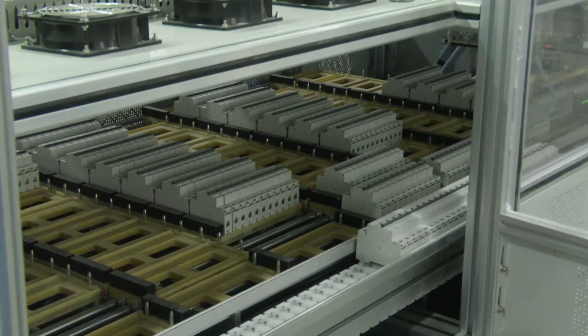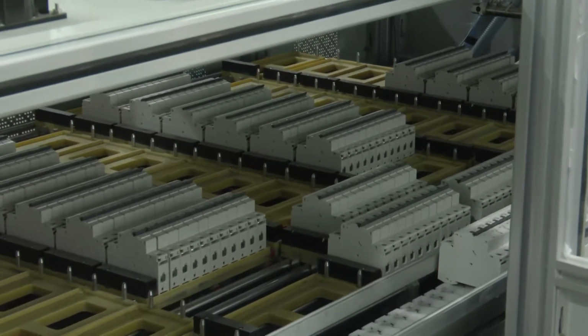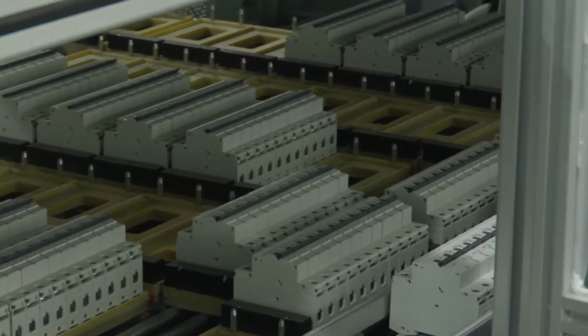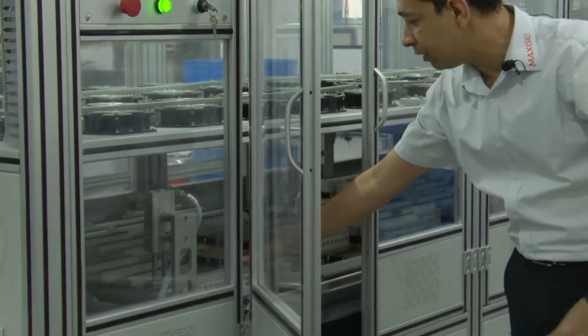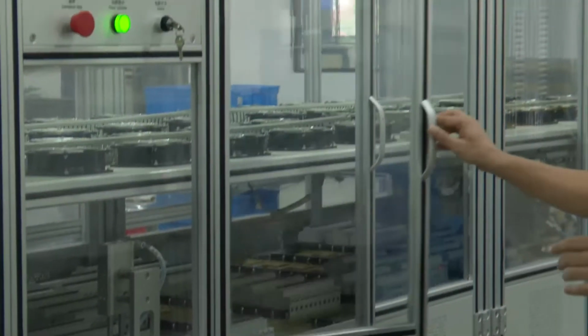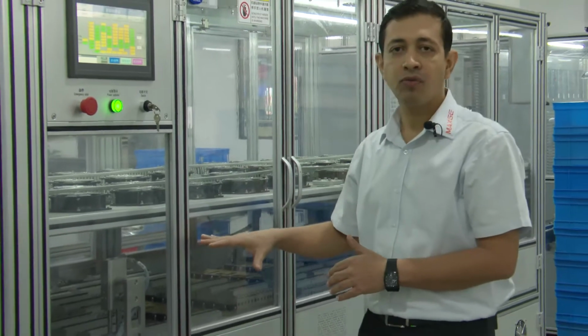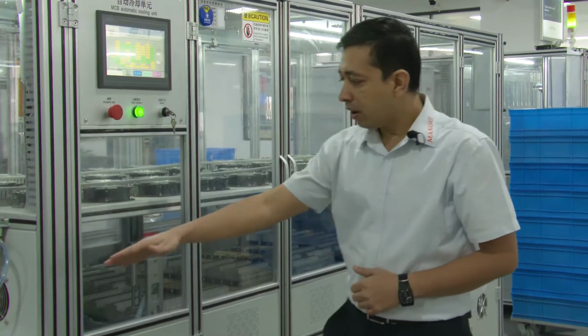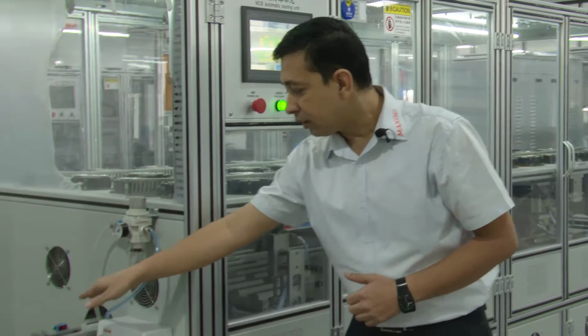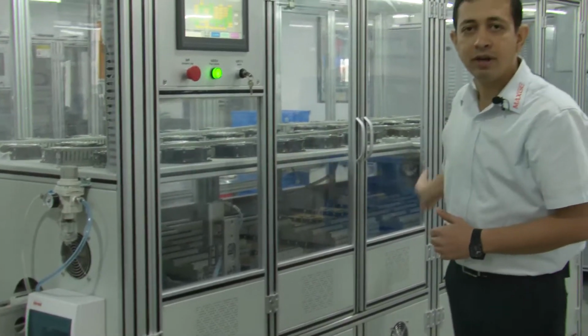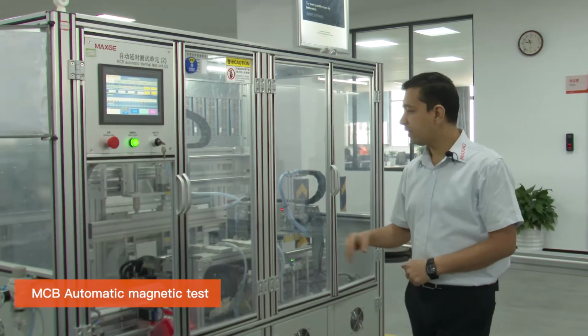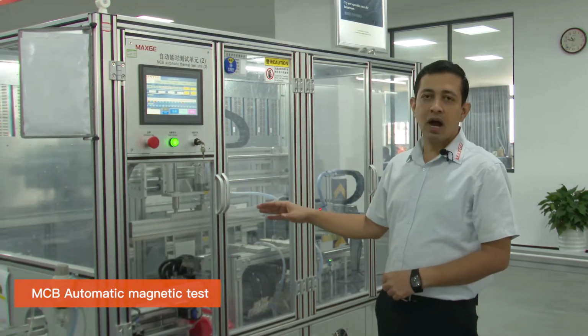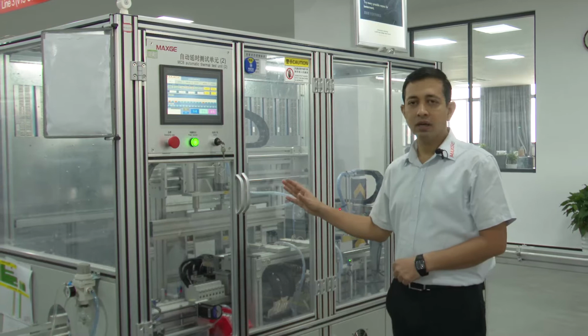You can see here there are many fixtures mounted, and in one fixture there are a total of 10 MCBs. So we have programmed this machine to cool them for 45 minutes. Once the MCB goes in, it comes out after 45 minutes. So we can ensure that the bimetal is coming back to its original position before we test for the thermal verification. Now the next stage, after cooling, is the magnetic testing.